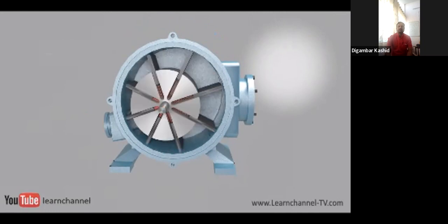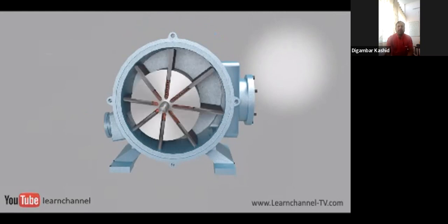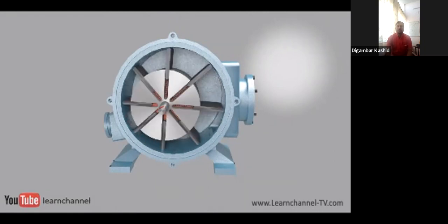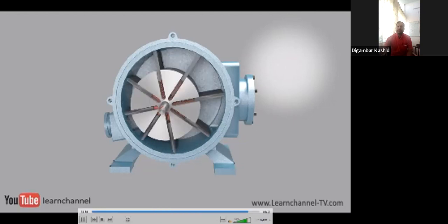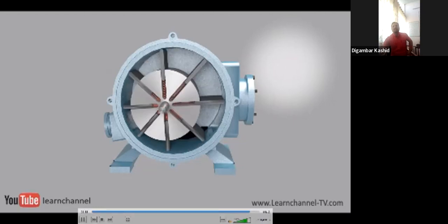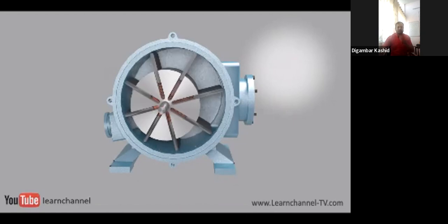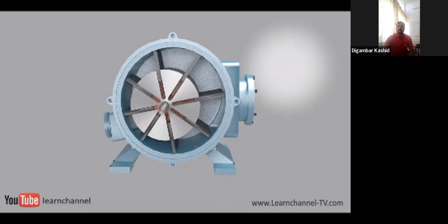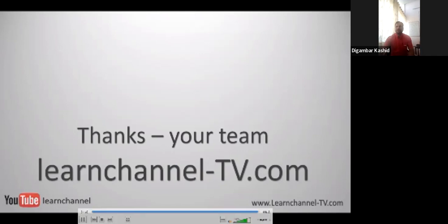The advantage here is the pulsation-free flow, in contrast to piston compressors. Therefore, an air tank may be optional. In addition, these compressors are quiet and relatively insensitive to dirt. Typical applications are, for example, wastewater treatment, fish breeding aeration, dust collection, vacuum packing, and so on. Watch also our next videos.